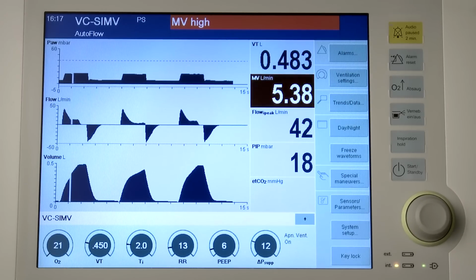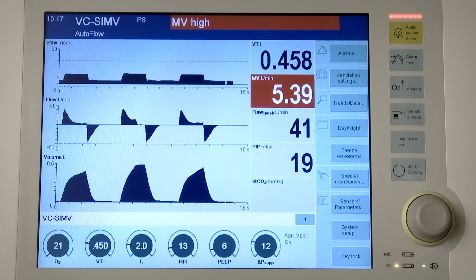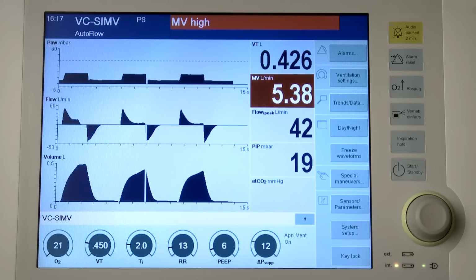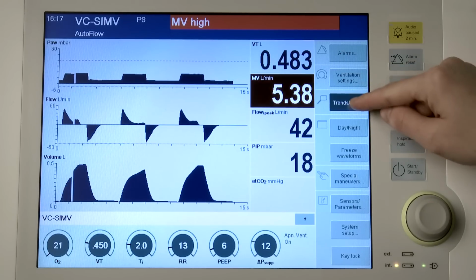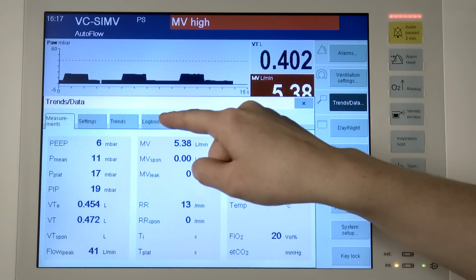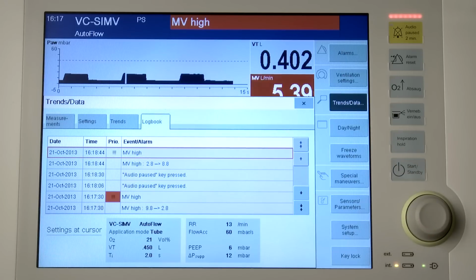High-priority alarm messages that are no longer active are displayed in the background color of the alarm message field. The parameter box of the parameter triggering the alarm flashes in the color of the alarm priority. Red means warning and is an alarm with high priority. Yellow means caution and is an alarm with medium priority. Cyan means note and is an alarm with low priority. On the logbook page, the priority of the alarm messages is also indicated by exclamation marks.